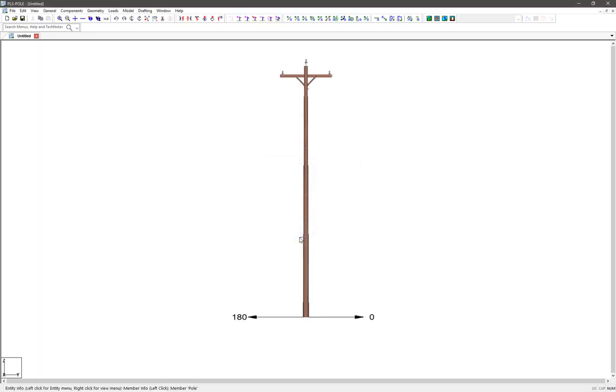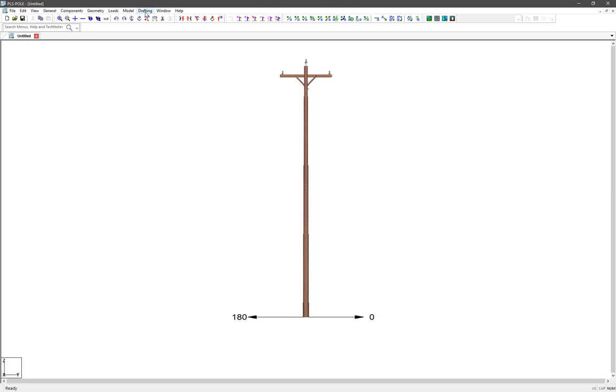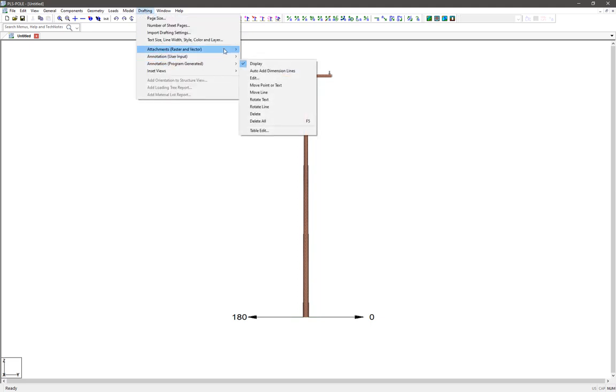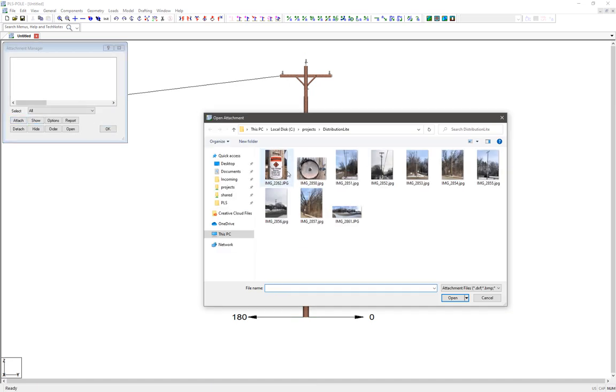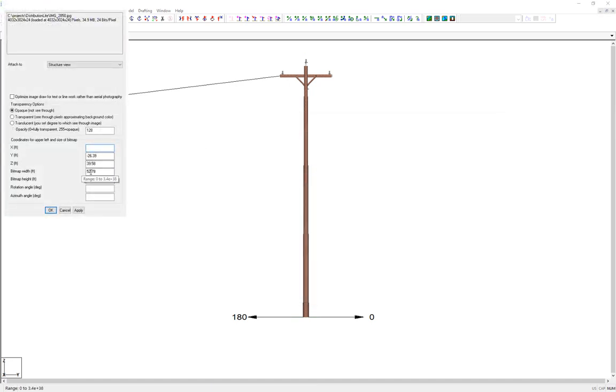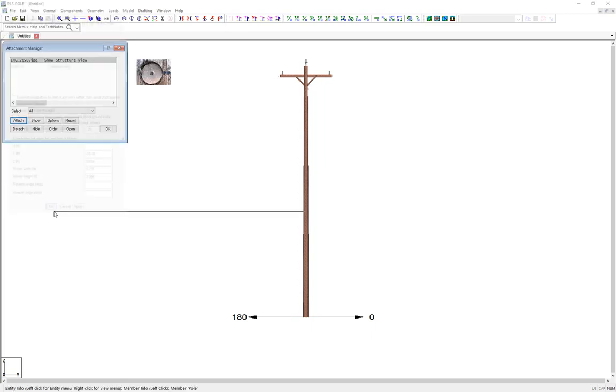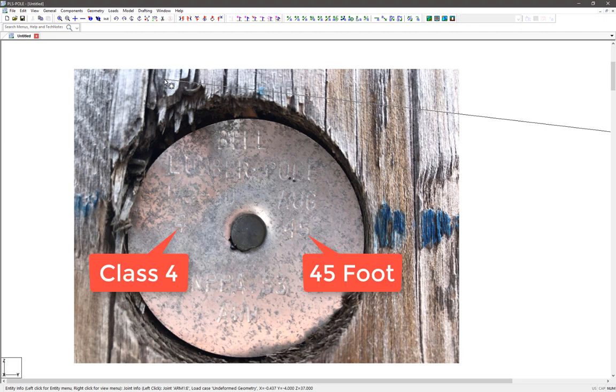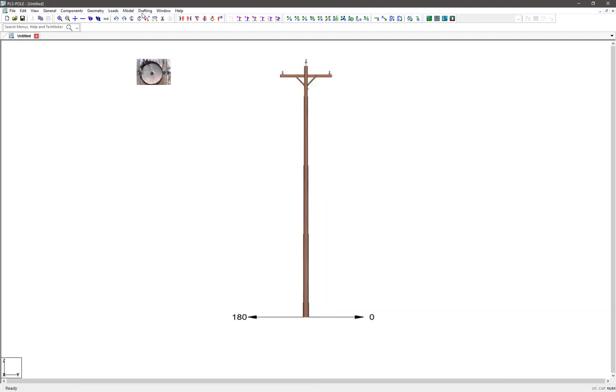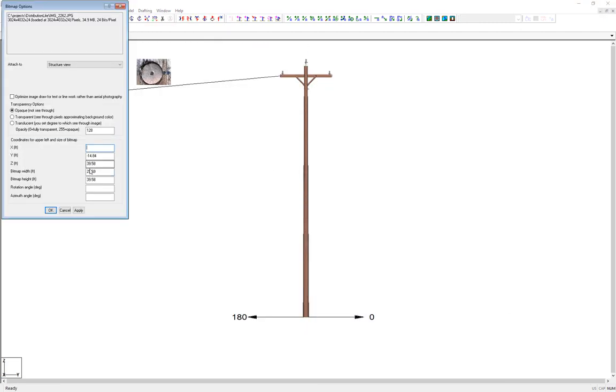Now before we add in the communication wire attachment, let's first bring in some of our photos we took of the structure during our site visit so that we can calibrate them and verify the framing. I'll go to the Drafting Attachments Attachment Manager, then click on the Attach button. I'll first attach the pole tag picture, 2850, that shows it's a 45-foot Class 4 pole, and I'll attach it to the structure view but shrink its default size down by a factor of 10 and click OK. Now I can zoom in on that picture and verify that it's a 45-foot Class 4. I'll also do the same thing for the pole tag picture.